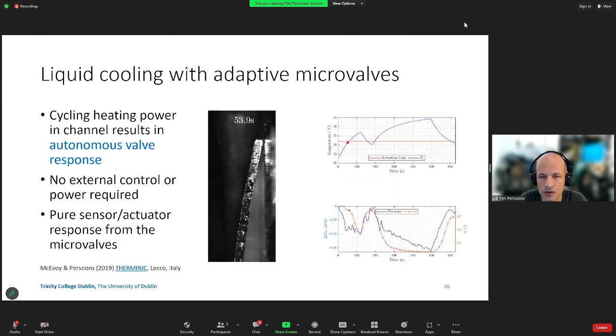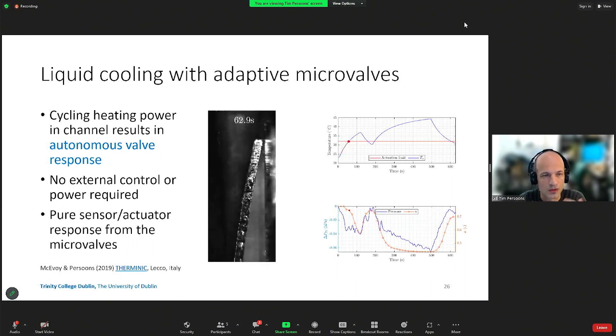And I'll just show you a sample of what that looks like. So the idea here is as the heatsink heats up under an increasing thermal load, these microvalves can change shape, and that can affect the pressure drop in the system. So more flow can be sent through a particular microchannel to compensate for that change in temperature. And so this allows for a completely autonomous valve response.